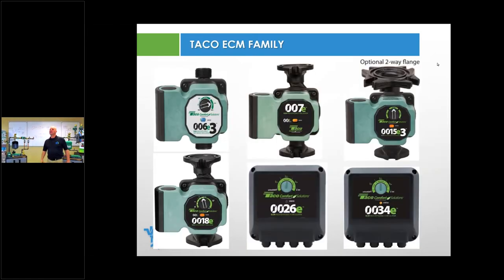We will keep going. So there is a whole realm of ECM circulators out there. I just want to make sure you guys are aware of what's available to you. So this is a little bit of product overview, but it's important. So that 006E right there, that is a recirculation style circulator. It will marry up to a lot of different systems. Right on the box, it will tell you what it will marry up to. We have complete recirculation systems available with what's called a little hot link. It'll go underneath the sink if you don't have a dedicated return line. As long as you have a tank style water heater, you can use one of those circulators with a hot link.